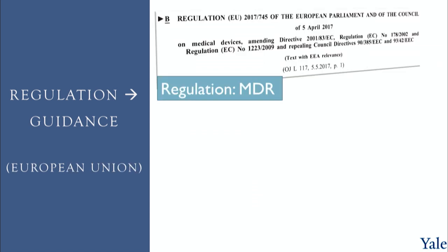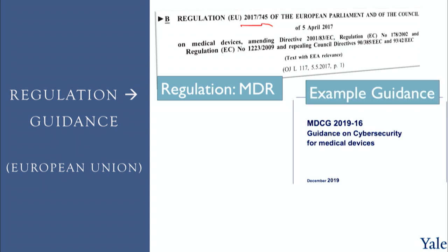The same process applies in the European Union. The regulation is the Medical Device Regulation 2017-745 that just came into effect in May of 2021. Here's an example guidance. It's a guidance from the European Union on cybersecurity in medical devices.